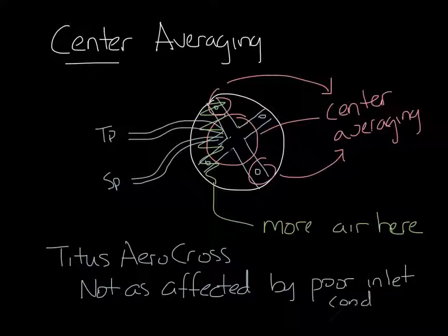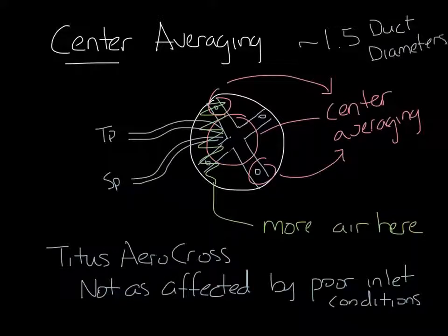Because of this, you need less straight duct into the box inlet, about 1.5 duct diameters for our flow sensor, compared to about 3 duct diameters for a linear averaging type sensor.